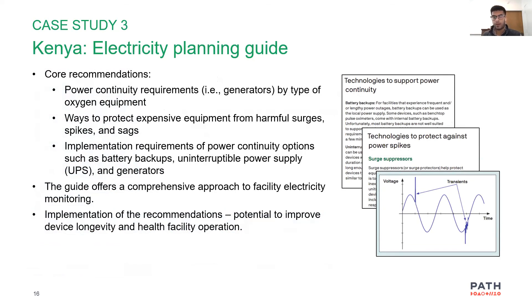Key recommendations from the Kenya example include ensuring that facilities have power continuity. The guide goes in depth on different power continuity options — generators are a great example. There are also uninterrupted power supply (UPS) devices, especially important in the oxygen context when patients reliant on a concentrator or on-site PSA plant cannot have their oxygen supply interrupted by an outage. Voltage protection and surge protection devices are also critical to ensuring equipment isn't damaged when grid power cuts out. This guide provides a comprehensive approach to facility electricity monitoring and implementing recommendations to ensure devices can continue to be used effectively.